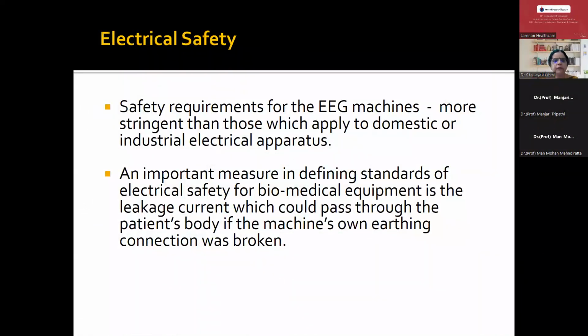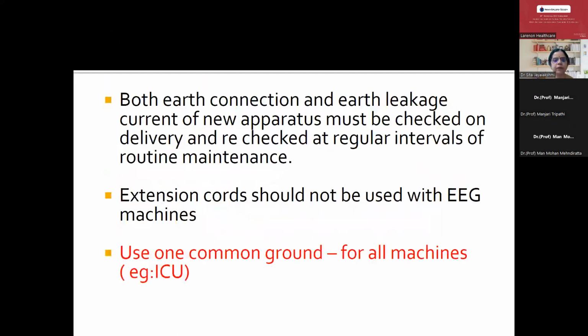The last part is the electrical safety of the machine. This is very important, because we do see some accidents happening in the EEG labs. So it is important to define the standards of electrical safety for biomedical equipment. We should also make sure that there is no leakage of current which can pass through the patient's body if the machine's own earthing connection is broken. So earthing is very important whenever an EEG lab is established. Also, extension cords should never be used with EEG machines.